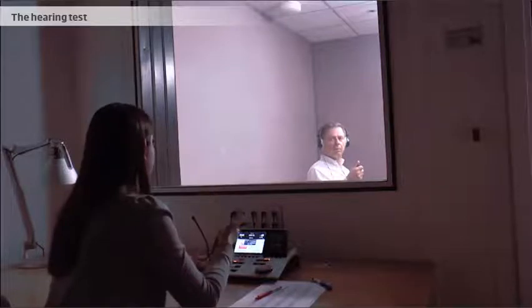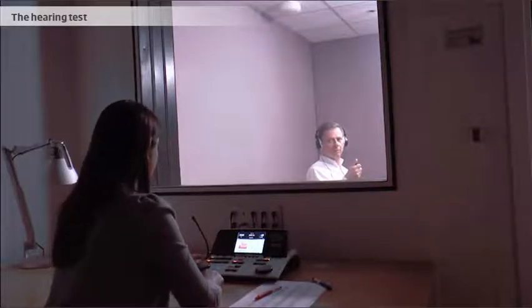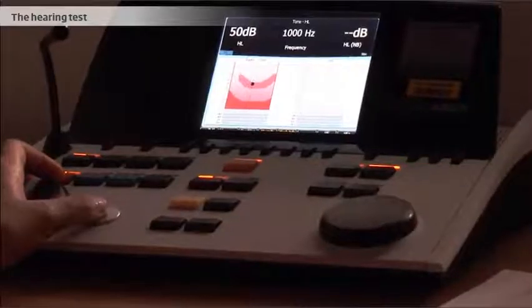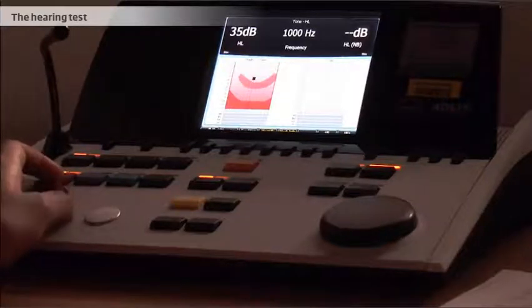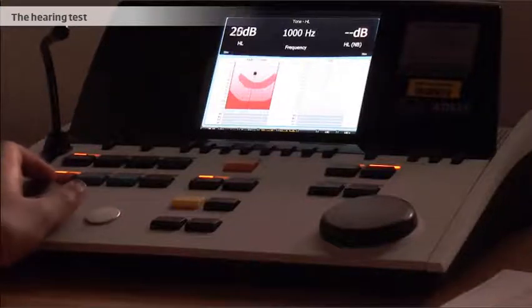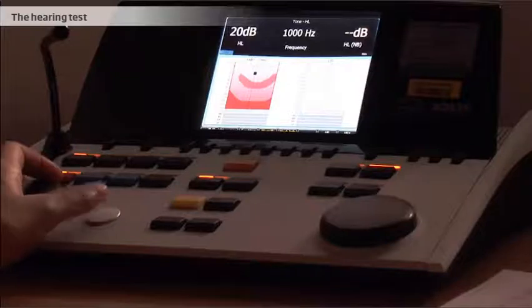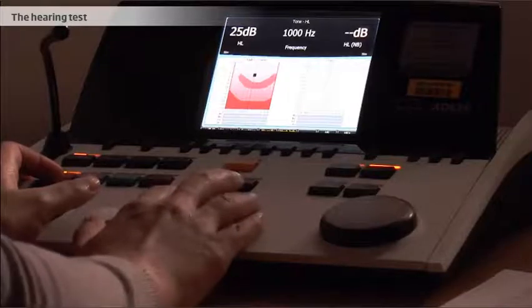It is important that the hearing care professional can see the client during the entire test. The hearing care professional will speak to the client through the headset to re-instruct the client regarding the test and to indicate that the test will begin. The hearing care professional uses an audiometer to conduct the test. The audiometer delivers tones of varying frequency and levels. The sound levels are increased and decreased following a specific procedure. The client responds by pressing the button when a sound is heard.